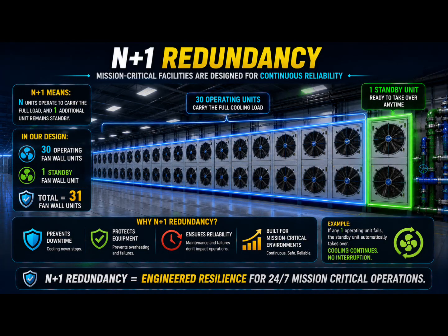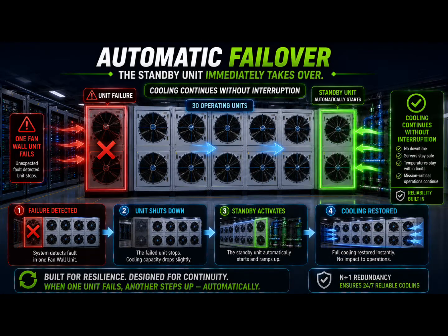The calculation is simple. 30 units carry the full cooling load. One additional unit remains available as a standby. If any operating unit is removed for maintenance or experiences an unexpected fault, the standby unit immediately takes over. No interruption, no overheating, no downtime. To everyone outside the building, nothing appears to have changed. But inside, the cooling system has quietly protected the entire data hall.